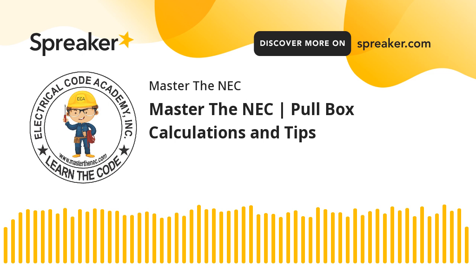Now, it doesn't matter whether it's left to right or they come into the bottom and go out the top. That's a straight pull. Now, the one thing that people ask me all the time about these pulls is, okay, Paul, what's the depth of the box? And if it's a straight pull, what's the height of the box? What's the Y dimension since you have no Y dimension calculation? And what's the depth of the box? The reality is there is no rule on that.